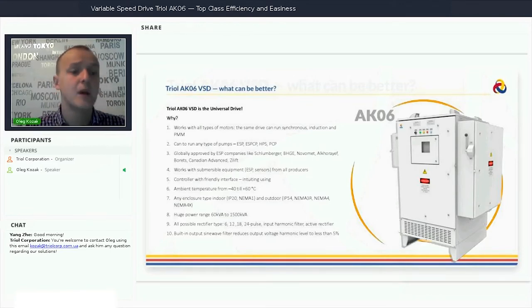We have our own designs, already proven from the smallest to the biggest solutions. We offer any type of rectifier to match the THD level, from 6, 12, 18, 24 pulse, built-in input harmonic filter, and active rectifier, which is mostly used for PCP.